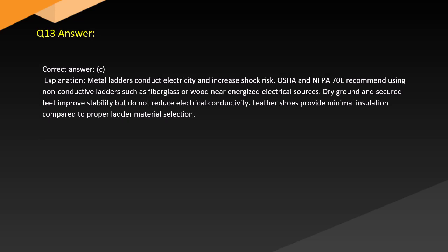Answer. Correct answer: C. Explanation. Metal ladders conduct electricity and increase shock risk. OSHA and NFPA 70E recommend using non-conductive ladders, such as fiberglass or wood, near energized electrical sources. Dry ground and secured feet improve stability but do not reduce electrical conductivity. Leather shoes provide minimal insulation compared to proper ladder material selection.